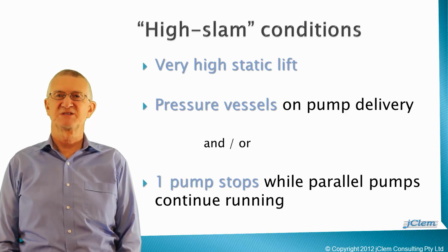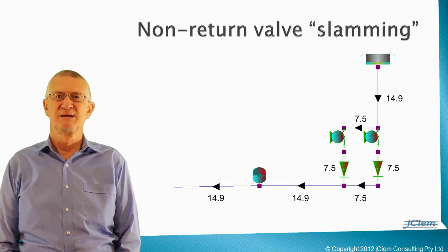Whenever a single pump stops and there are other parallel pumps in the station which continue to run. This is a very common scenario where the high head generated by the running pumps is almost instantaneously imposed on the stopped pump. Let's take a few moments to understand what is happening when a pump's non-return valve closes.